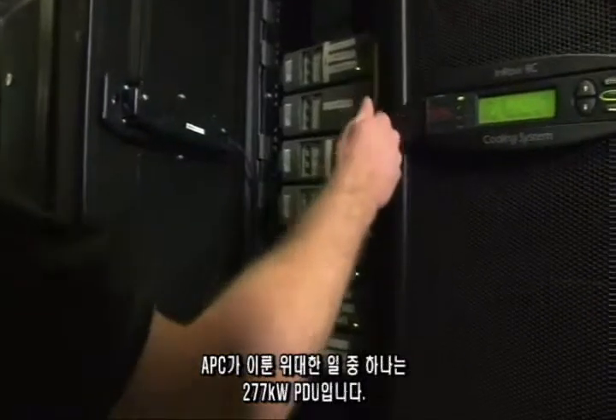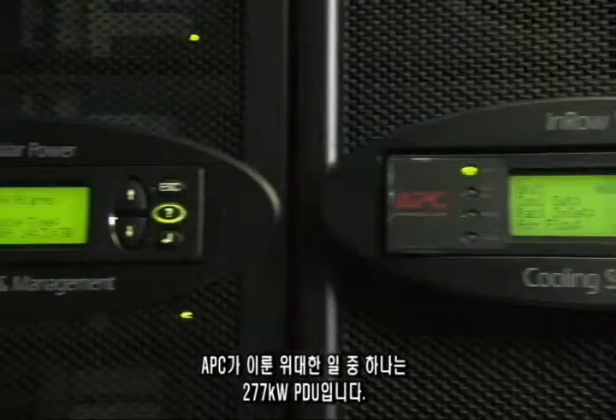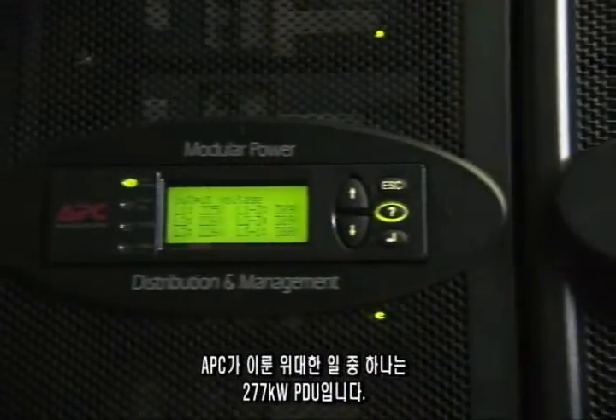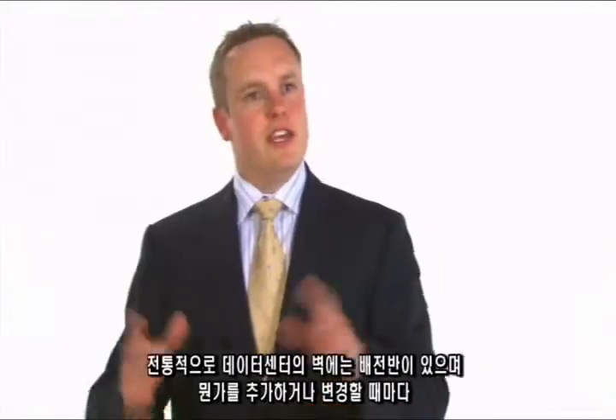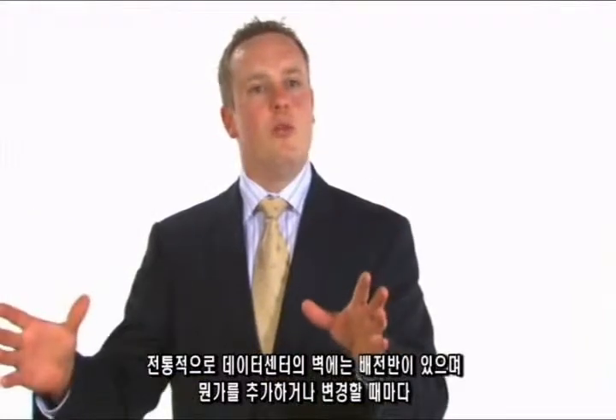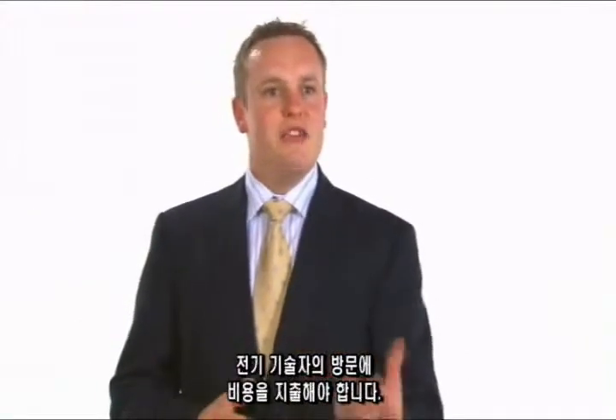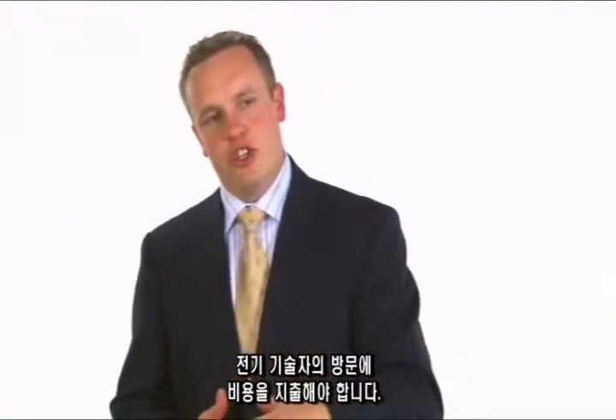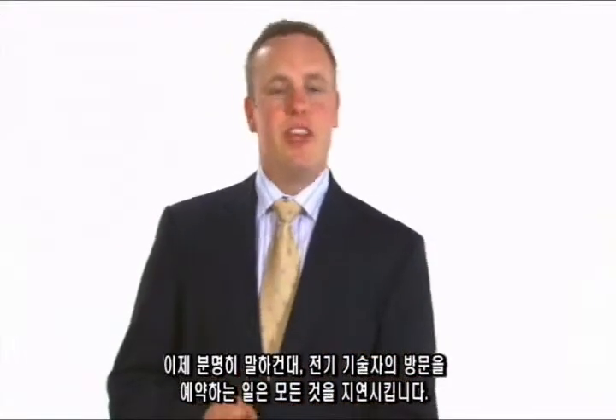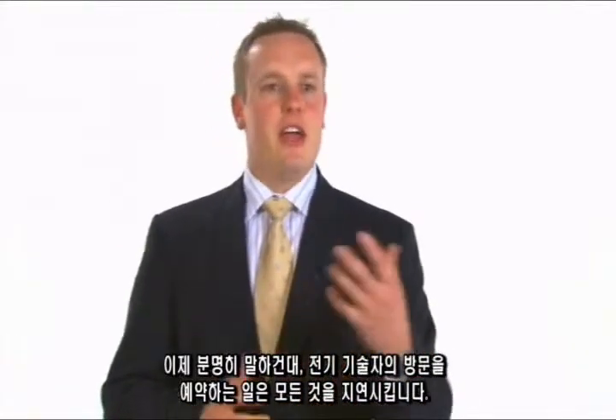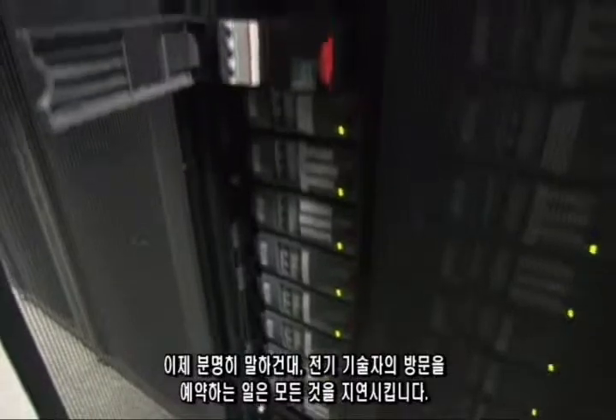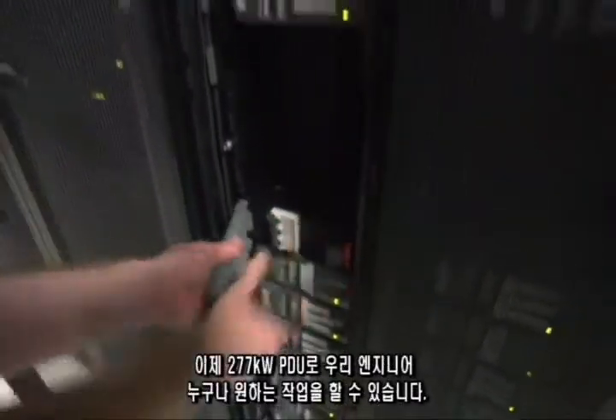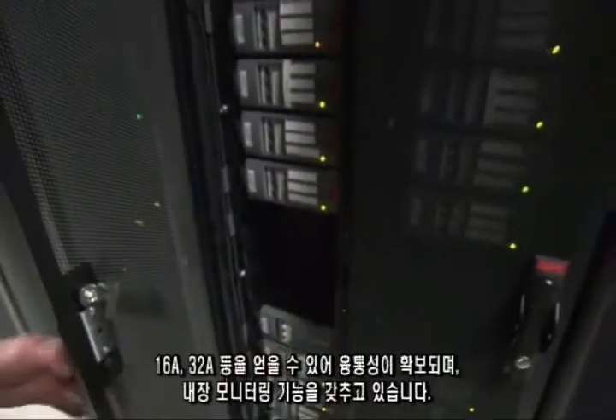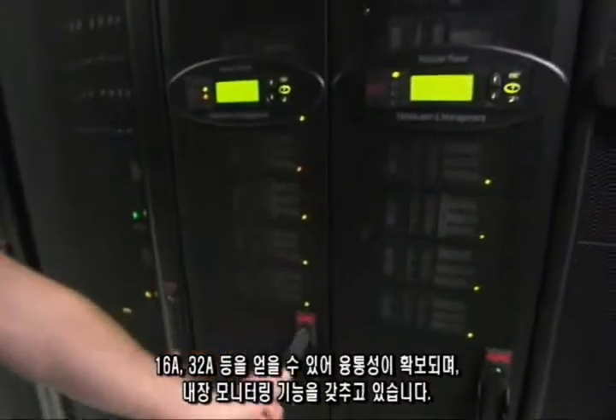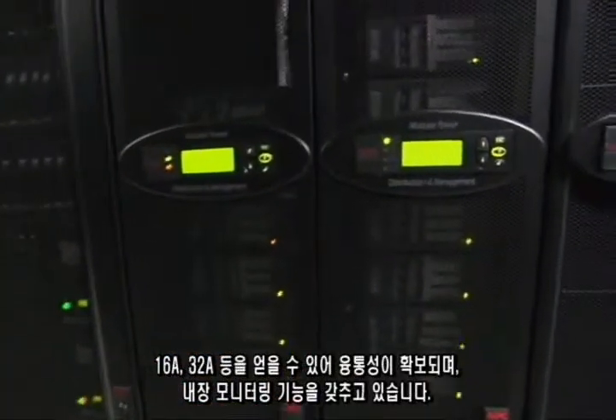One of the great pieces of kit that APC brought out is the 277 kilowatt PDU. Traditionally, in a data centre, you'd have a switchboard on the wall, and every time you wanted to add or change something, you'd be paying for an electrician to come in. Now, obviously you'd have to book the electrician, it delays everything. With the 277 kilowatt PDU, any one of my engineers can just go down there, plug a whip in, and it's really flexible. We can get 16 amp, 32 amp, and the other great thing is it's got built-in monitoring.